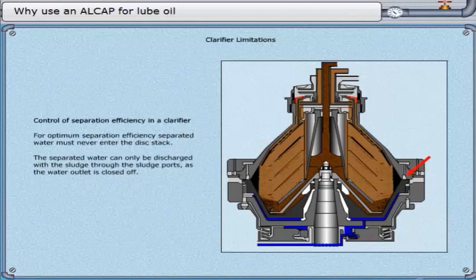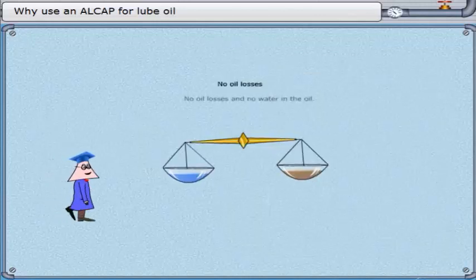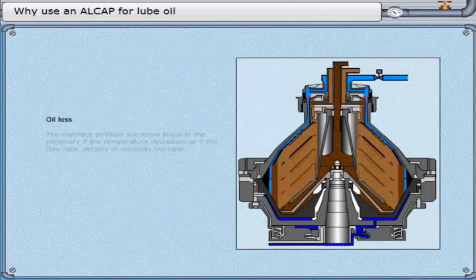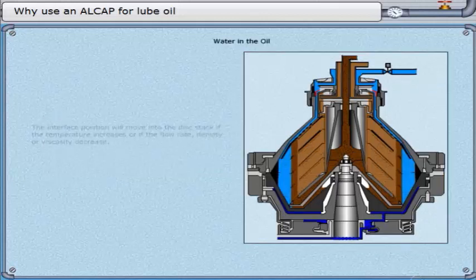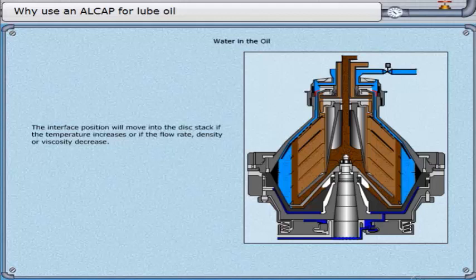The separated water can only be discharged with the sludge through the sludge ports, as the water outlet is closed off — resulting in no oil losses and no water in the oil. The interface position will move towards the periphery if the temperature decreases, or if the flow rate, density, or viscosity increase. Should the interface reach the outside of the top disc, a broken water seal will occur with consequent oil loss. The interface position will move into the disk stack if the temperature increases, or if the flow rate, density, or viscosity decrease. Should the interface enter the disk stack, water will escape with the cleaned oil into the oil outlet.